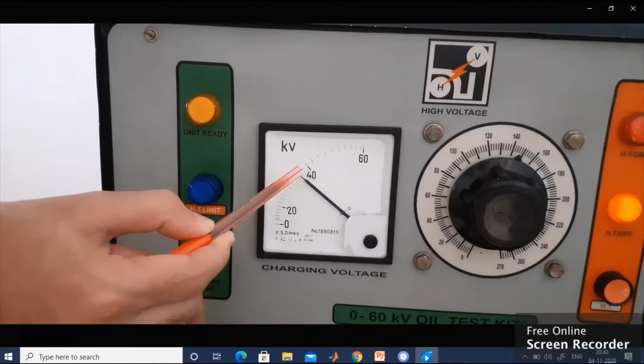At a particular voltage, breakdown will happen in the transformer oil, which is a liquid dielectric material. Moreover, breakdown is temporary - after a certain time, it will regain its original property, after 15, 10 or 20 minutes. Similarly, you have to go for another 5 to 6 readings and take an average finally. So that is the procedure.